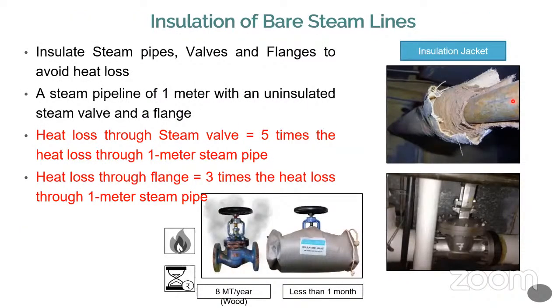Insulation is another important factor where you need to find out whether the insulation is properly done or not. The piping system should be properly insulated. Not only the pipes, the flanges and the valves, everything should be properly insulated. But most of the time, pipes are properly insulated, but the flanges and valves are not properly insulated.